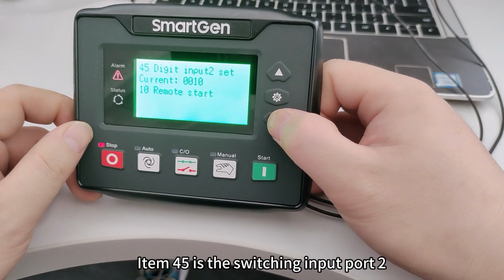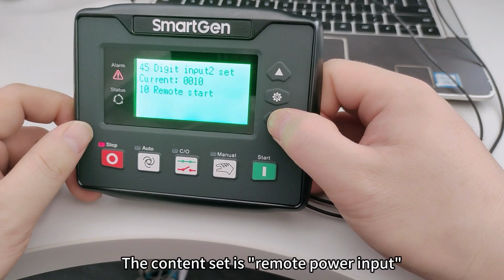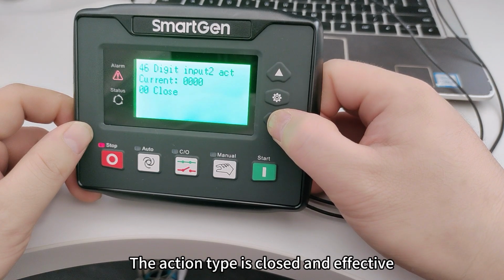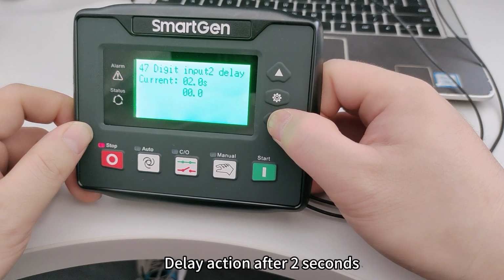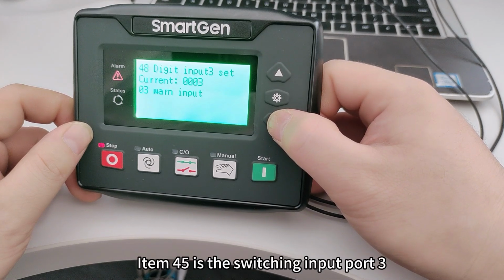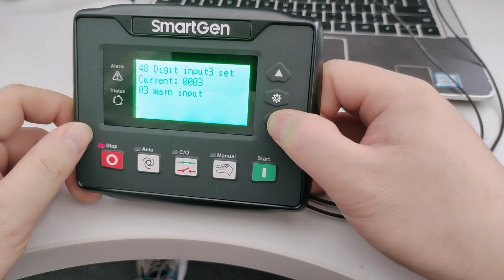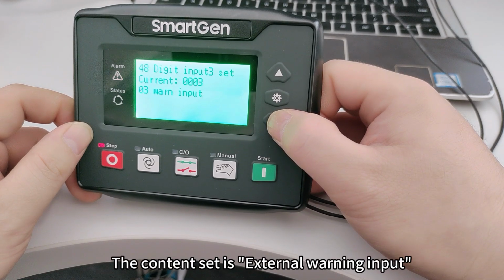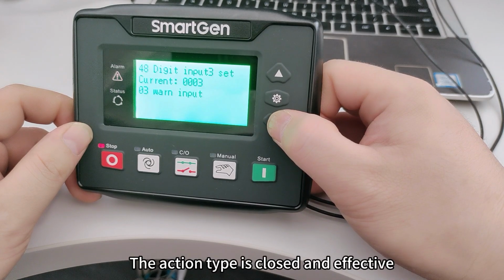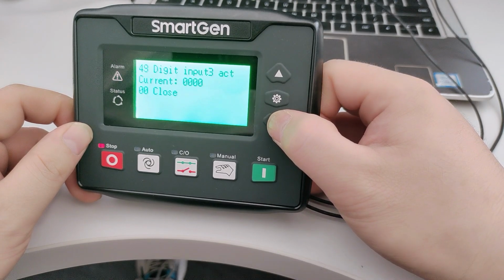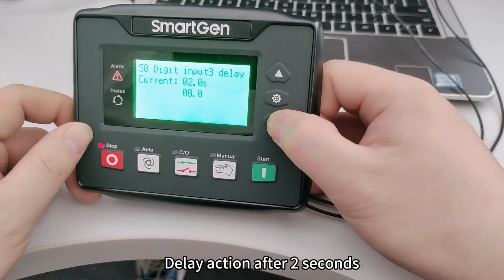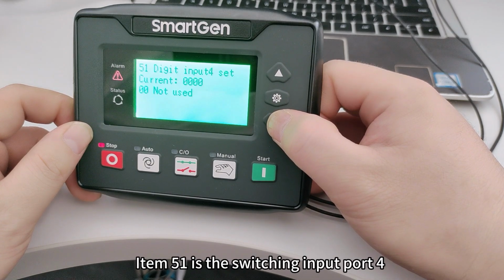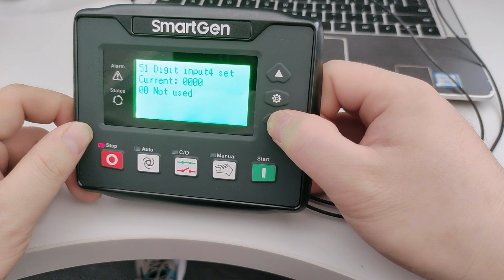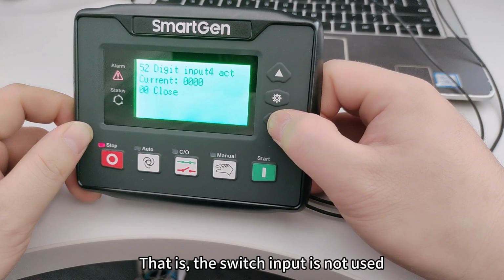Item 45 is the switching input port 2. The content set is remote start input. The action type is closed and effective. Delay action after 2 seconds. Item 48 is the switching input port 3. The content set is external warning input. The action type is closed and effective. Delay action after 2 seconds. Item 51 is the switching input port 4. The content set is unused, that is, the switch input is not used.